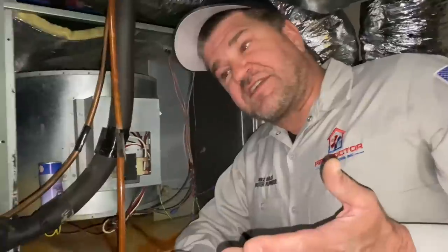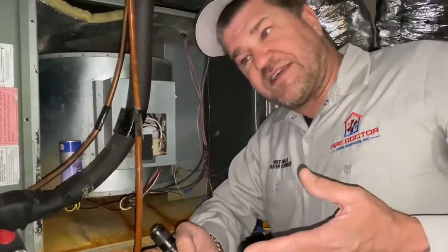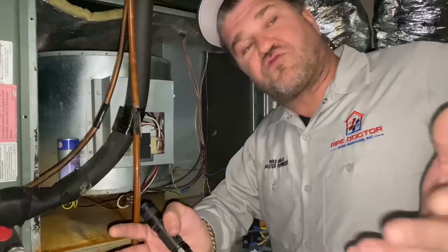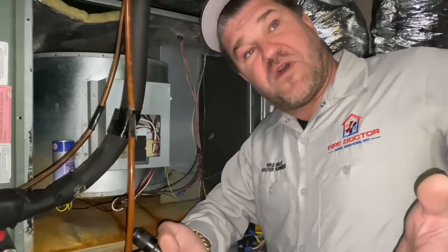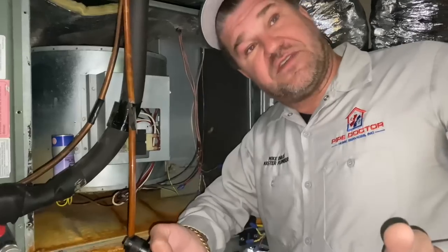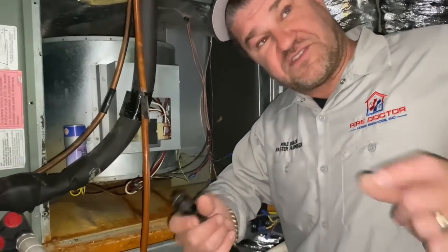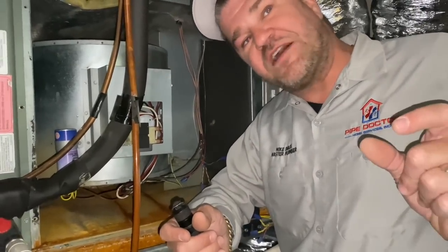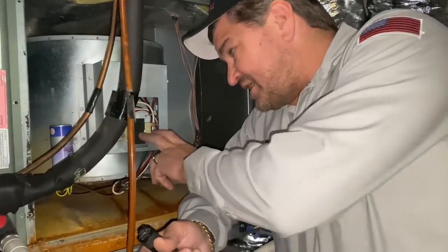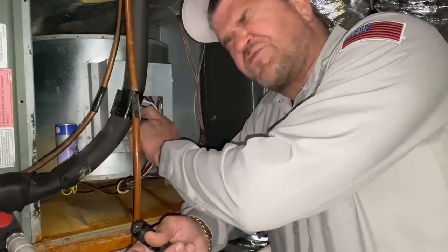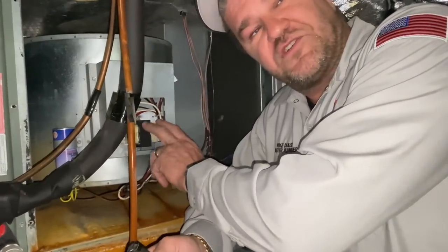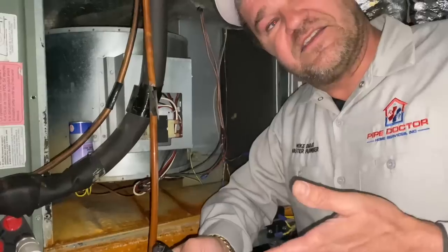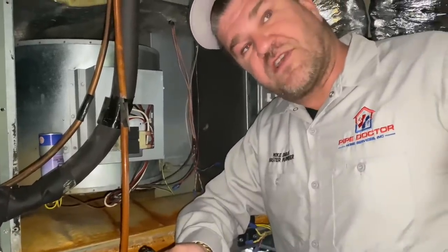Yes. So to put it into perspective with a safety circuit, picture a rollout switch being like a fuse. It protects the boiler if something goes wrong with flame rollout, because technically a rollout switch is a fusible link. So the transformers we install, the ones by Honeywell, have a little circuit breaker built into them, giving added protection to the transformer.